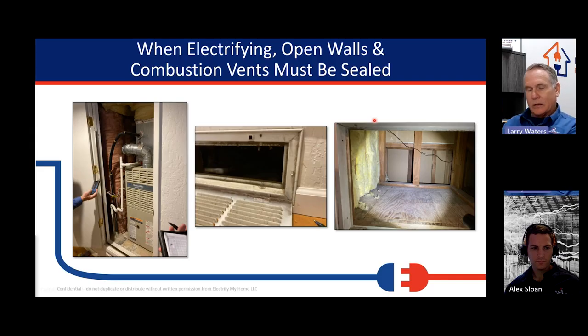We need to bring that closet back into the house, because when you have a furnace closet with ventilation, upper and lower combustion air, that closet is theoretically outside the building envelope. It's really existing between the attic and the underfloor. And sometimes we go to those things and we have an ill-fitting door.